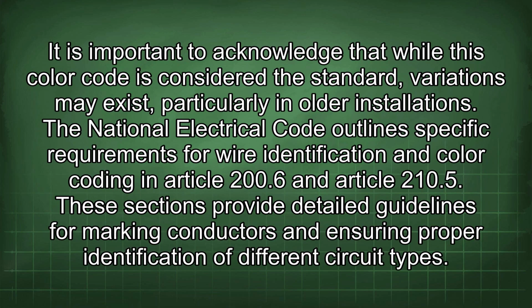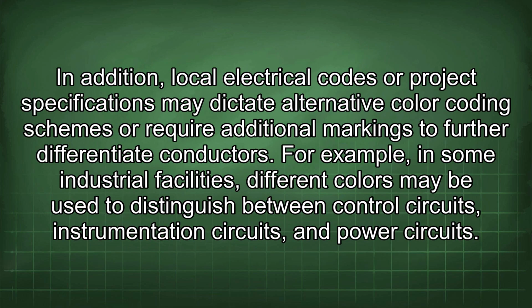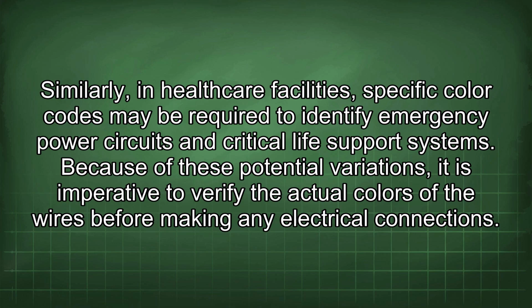It is important to acknowledge that while this color code is considered the standard, variations may exist, particularly in older installations. The National Electrical Code outlines specific requirements for wire identification and color coding in Article 200.6 and Article 210.5. These sections provide detailed guidelines for marking conductors and ensuring proper identification of different circuit types. In addition, local electrical codes or project specifications may dictate alternative color coding schemes or require additional markings to further differentiate conductors. For example, in some industrial facilities, different colors may be used to distinguish between control circuits, instrumentation circuits, and power circuits. Similarly, in healthcare facilities, specific color codes may be required to identify emergency power circuits and critical life support systems.